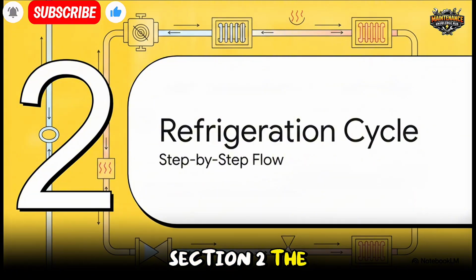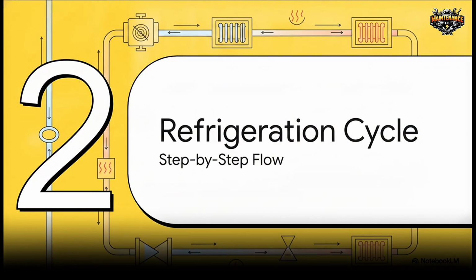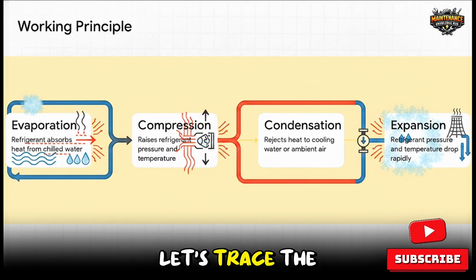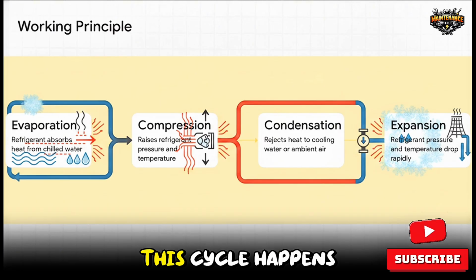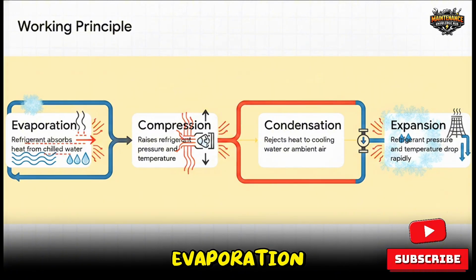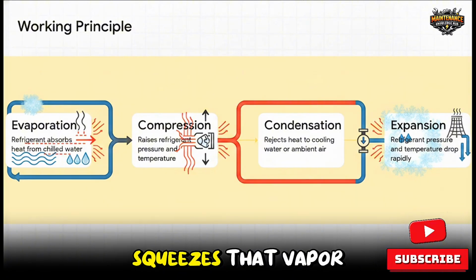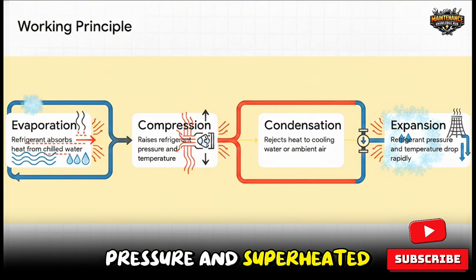Section 2. The refrigeration cycle. Now that we know the organs, let's trace the exact step-by-step journey of the refrigerant as it flows through. This cycle happens in 4 dynamic steps. Step 1 is evaporation. Here, the refrigerant acts almost like a heat thief. It absorbs heat from the warm return water in the evaporator, boiling and changing from a liquid into a vapor. Step 2 is compression, where our heart squeezes that vapor, making it high pressure and superheated.